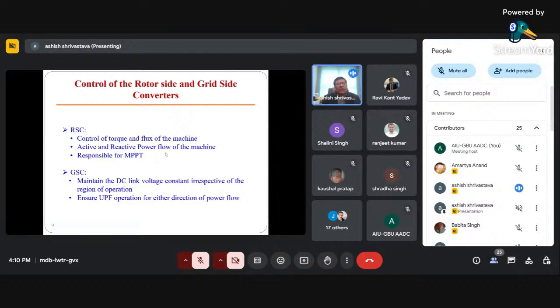As I said, there are two kinds of converter: the rotor side converter and the grid side converter. The one close to the grid is called the grid side converter, which has the purpose of converting AC into DC, and the rotor side converter is for DC into AC. That's where you can control both sides. The RSC is responsible for controlling the torque and the flux of the machine. The rotor side converter can also control active and reactive power flow of the machine, and it is also responsible for MPPT. That means you can share the requirement and the load. So MPPT will be taken care of by the RSC, and unity power factor will be taken care of by the GSC, that means the grid side converter.